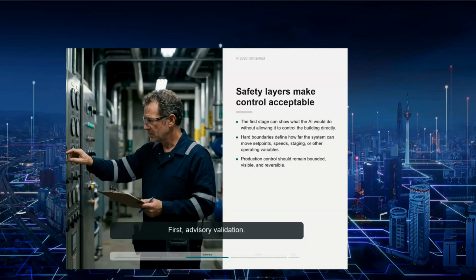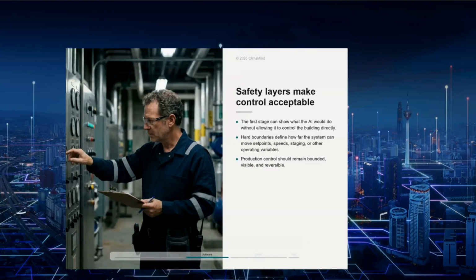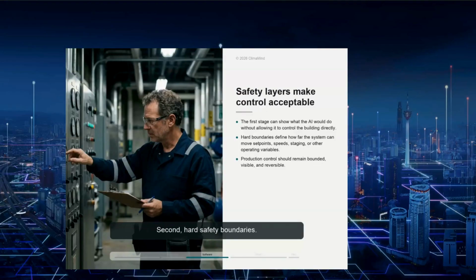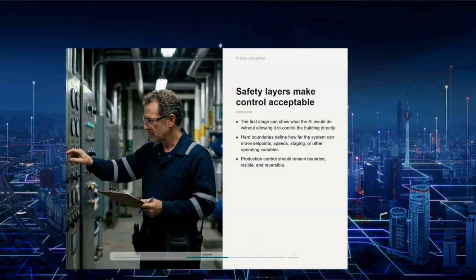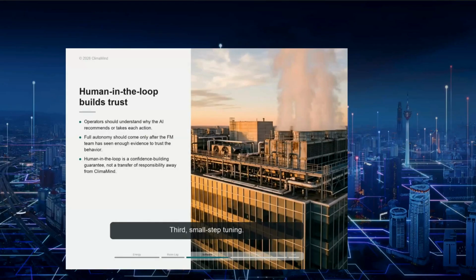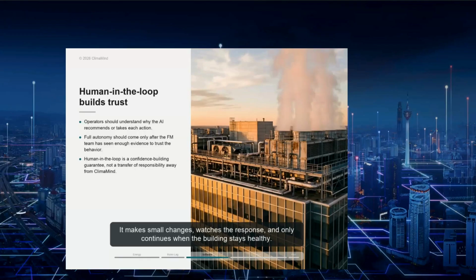First, advisory validation. Before control is enabled, it shows what the AI would have done, what effect it expects, and why the move stays safe. Second, hard safety boundaries. The team defines what AI can touch, what range each value can move within, and what conditions stop optimization immediately. Third, small step tuning. The system does not make dramatic jumps. It makes small changes, watches the response, and only continues when the building stays healthy.